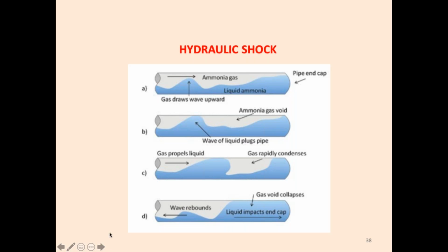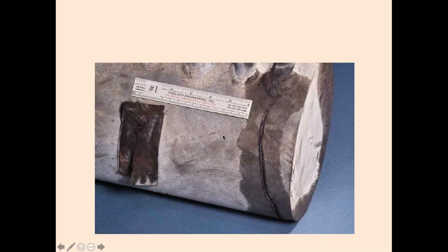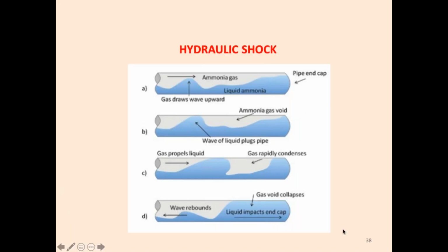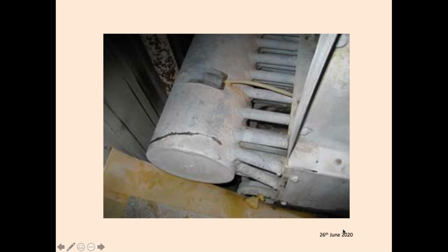Ammonia gas void has taken place. If you see in this slide, the gas is trapped. Now this gas rapidly condenses because the temperature is minus 40 degrees, minus 20 degrees, and then the liquid hammer takes place on the end cap. Because the liquid is trapped here, liquid impacts the end cap because there is no space, and this results in a very big failure. In one of my plants this has happened, because the person had put a valve in the LP line, and that valve was closed, and it created a problem.